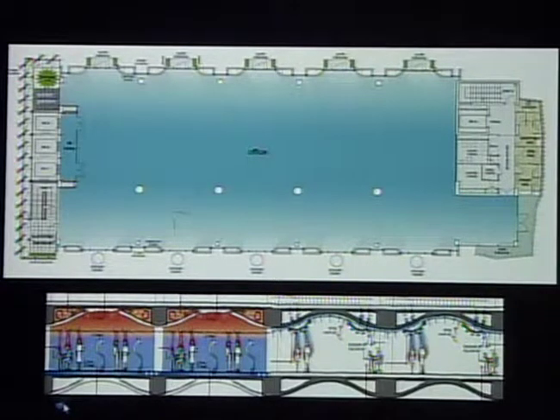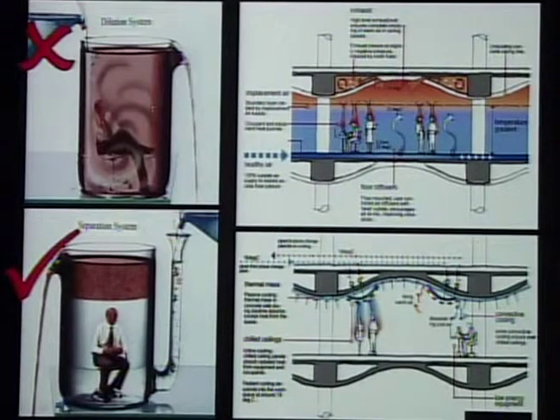The next slide shows the difference more explicitly. Top left is normal air conditioning, where you drop cold air on top of people's heads and recirculate it 6 air changes per hour. We do 2 air changes of 100% fresh air, and do the cooling mainly by radiance. We achieve that by cooling the wavy slab at night by opening windows, and the opening and shutting of those windows takes about 20% of the cooling load.